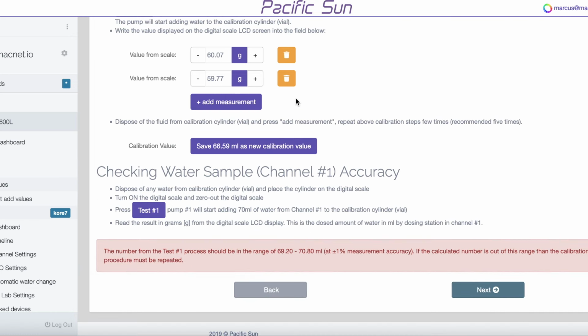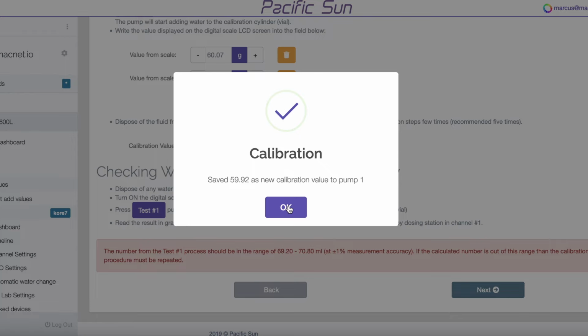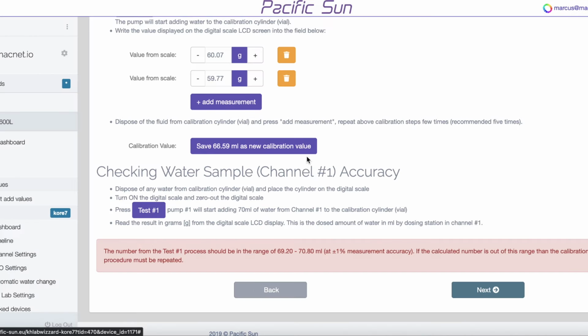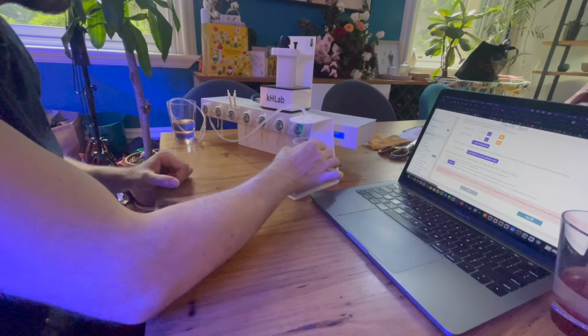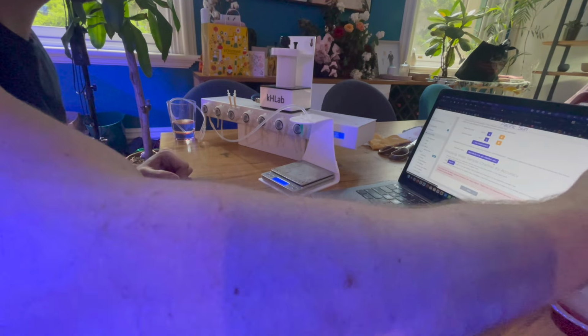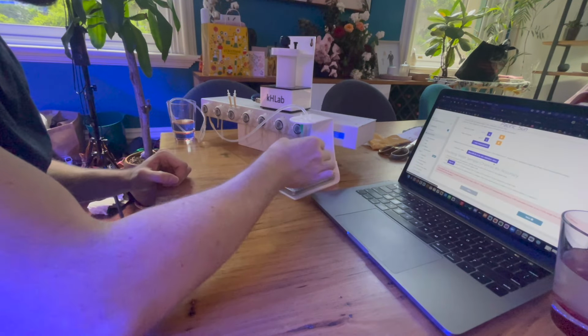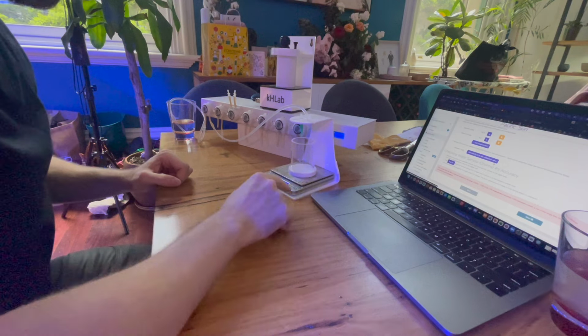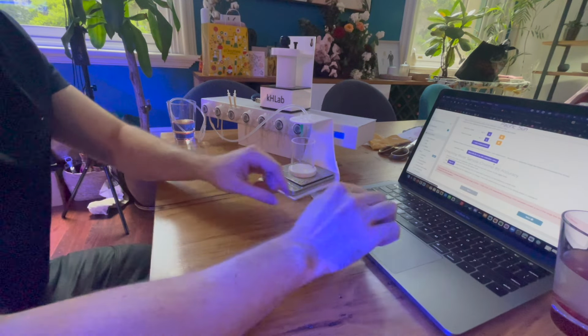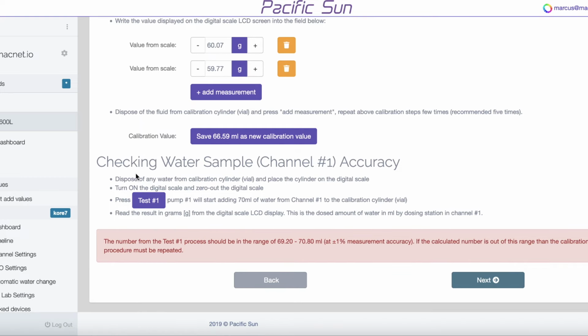Now, I'm only going to do 2 right now for the purposes of speed, but you would want to run this 5 times to get 5 values. So I'm going to save my calibration. There we go. I'm going to empty the water out of the cup. Tare the scale. And then finally, we're going to run the check.